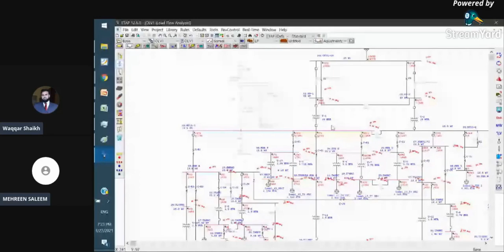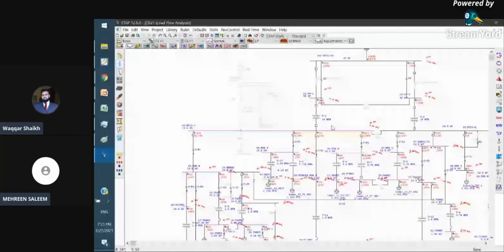So by running the simulation, what will happen? Because we have fewer power sources available, you will see that some of the network buses, especially those farther from the sources, because of the impedances, will suffer from voltage less than 95%, whereas the international standard says your voltage shall be minimum 95%. So when one of the generators was out of service, you have come across the problem of under voltage in the network. In fact, this is one of the most repeatedly found problems when we run simulations and investigate the network under any contingency condition.